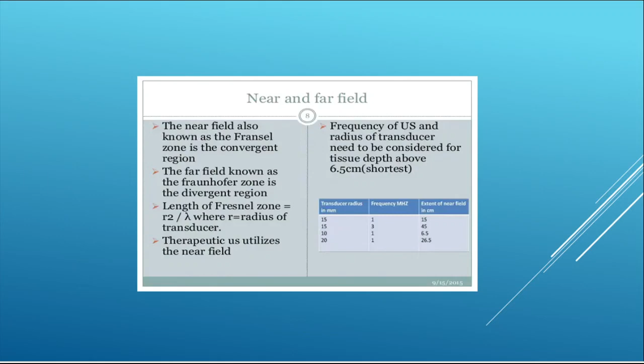The length of the near field depends directly on the square of the radius, as I have discussed, and the length of the Fresnel zone is r squared by lambda. The frequency of US and the radius of the transducer need to be considered for tissue depth above 6.5 centimeters. As for practical use, we are using the near field, and relatively more energy on average is carried in the central part of the cross section of the beam. The irregularities of the near field can be ignored, to some extent, by the continuous movement of the treatment head during the therapy.